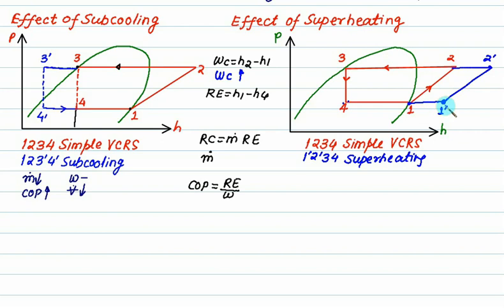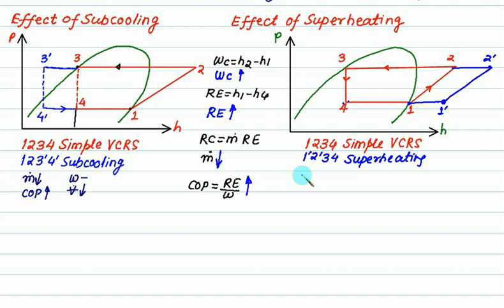With super-heating, the RE becomes h1-dash minus h4, so RE also increases. For the same RC, the mass flow rate will decrease. The COP improves slightly, depending on the percentage increase in RE versus the percentage increase in compressor work — but in fact, the RE percentage increase is always more than the compressor work increase. Summary: compressor work increases, RE increases, mass flow rate decreases, and COP improves.